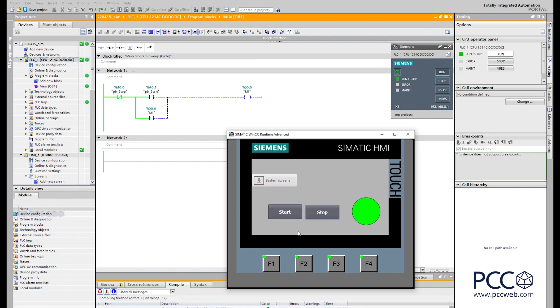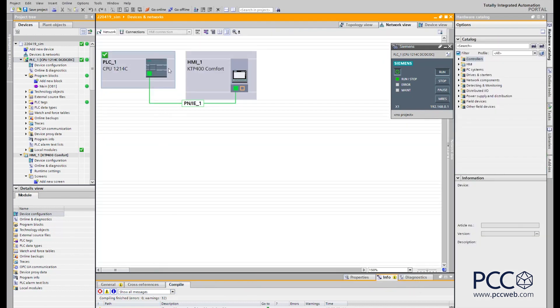As you can see — a very simple approach with no hardware in front of me — I'm able to simulate my logic and my HMI. One important point: I did not have to change out my hardware or my PLC. I've seen situations where, to use a simulator or emulation software, you actually have to change out the CPU in your program. I want to emphasize that is absolutely not the case in TIA portal and S7 PLCs. We can keep our project exactly as it would be in the field and simulate it as-is.